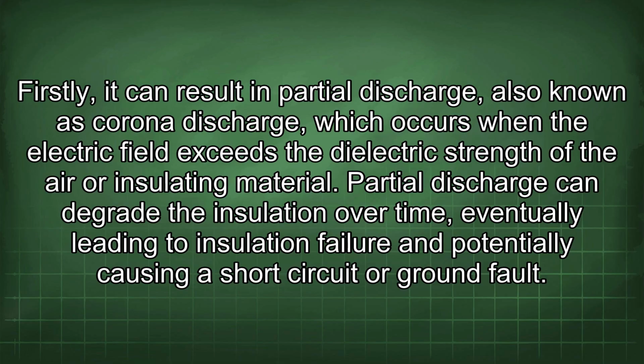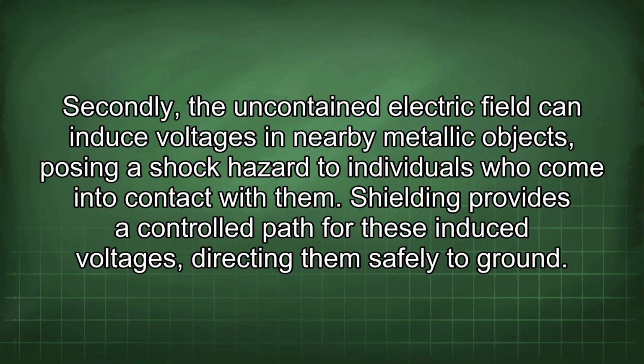Firstly, it can result in partial discharge, also known as corona discharge, which occurs when the electric field exceeds the dielectric strength of the air or insulating material. Partial discharge can degrade the insulation over time, eventually leading to insulation failure and potentially causing a short circuit or ground fault. Secondly, the uncontained electric field can induce voltages in nearby metallic objects, posing a shock hazard to individuals who come into contact with them. Shielding provides a controlled path for these induced voltages, directing them safely to ground.